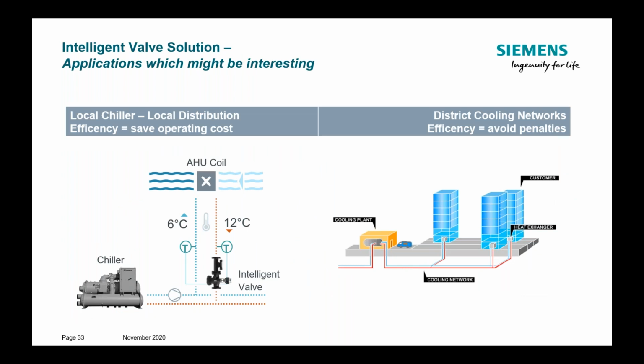And this 7% energy saving, there we have clearly two situations. We have local chiller installations with a local distribution. So the efficiency sums up in operational cost savings for the owner. And we have an additional effect if we are connected to networks, for instance, to district cooling networks, where usually the building owner or the operator has a contract with the utility and where he is forced to have only a certain power consumption for his building, and also more and more only to guarantee a certain return temperature or a certain DeltaT.